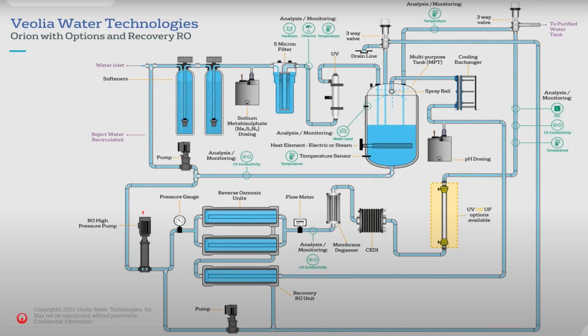The water then passes down to the reverse osmosis high pressure pump here. So the RO pump feeds the RO units. These two are the primary RO units in this particular schematic. On this particular unit, we're showing what we call the S version, which has the option for a recovery RO module to be installed in the system, which is the bottom unit you see here. So this takes the concentrate from the main RO and passes it through this unit. We recover the permeate back upstream of the RO into the tank here. Some of the concentrate gets fed around the system here, and the rest of it goes around this pipeline all the way around and out to drain here.